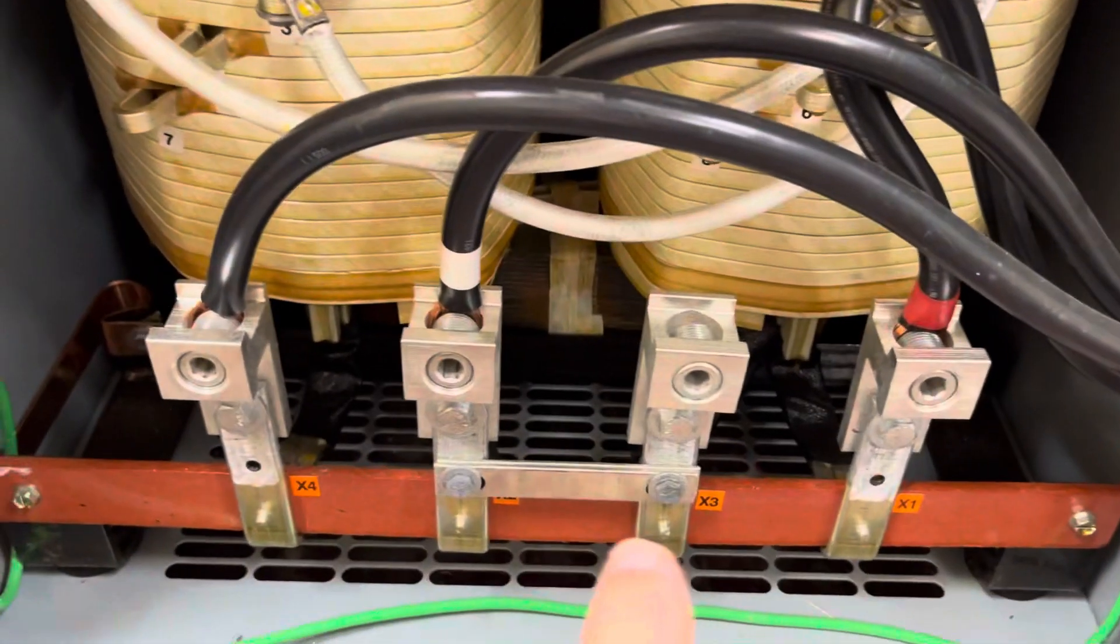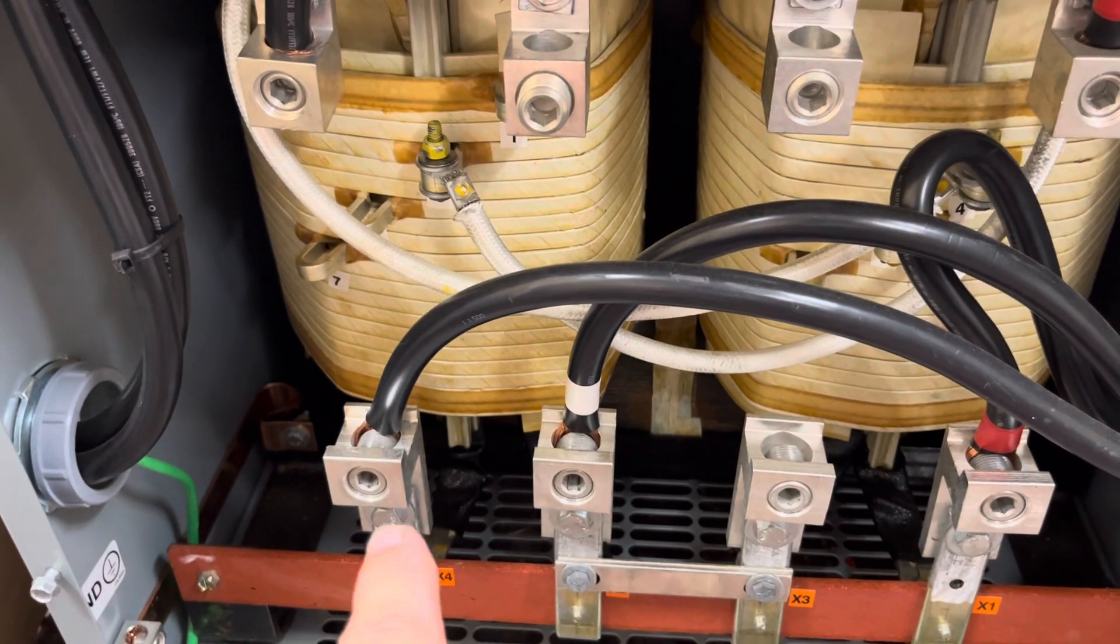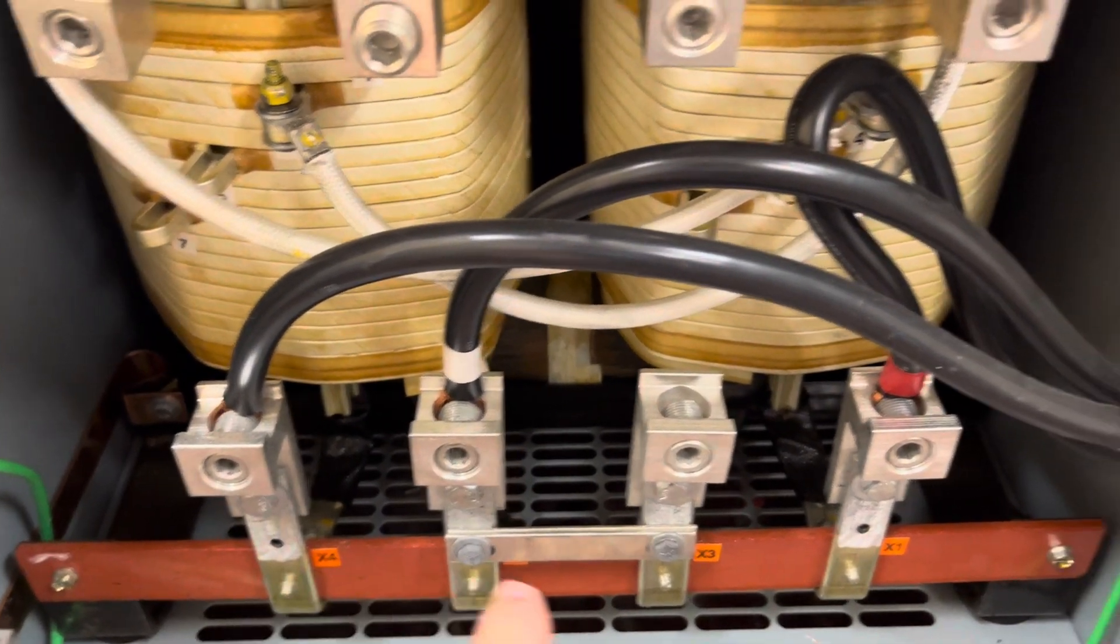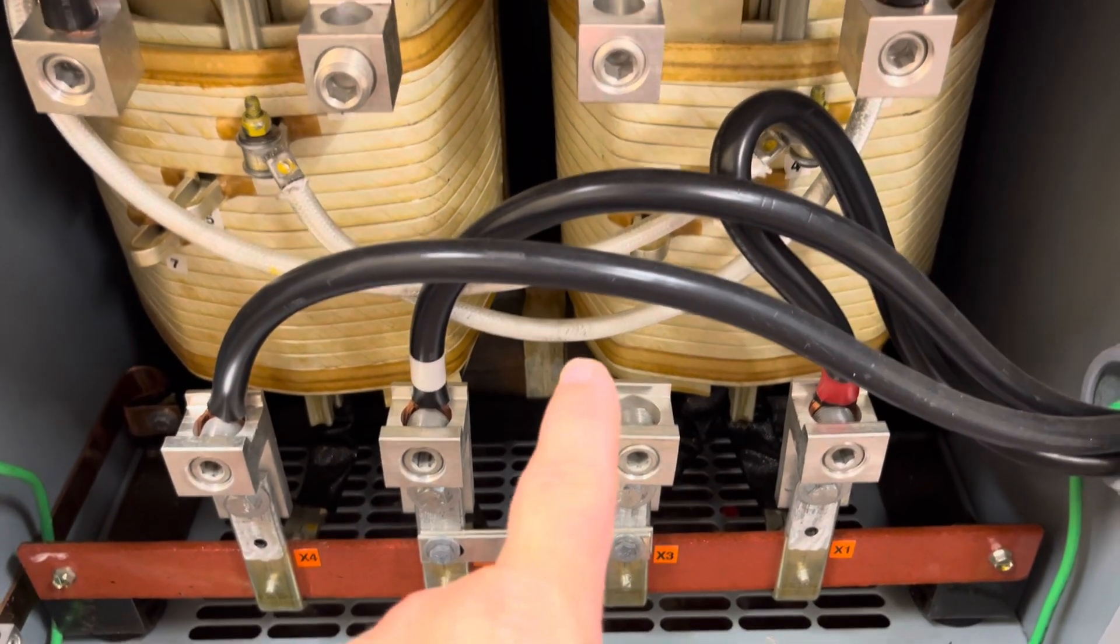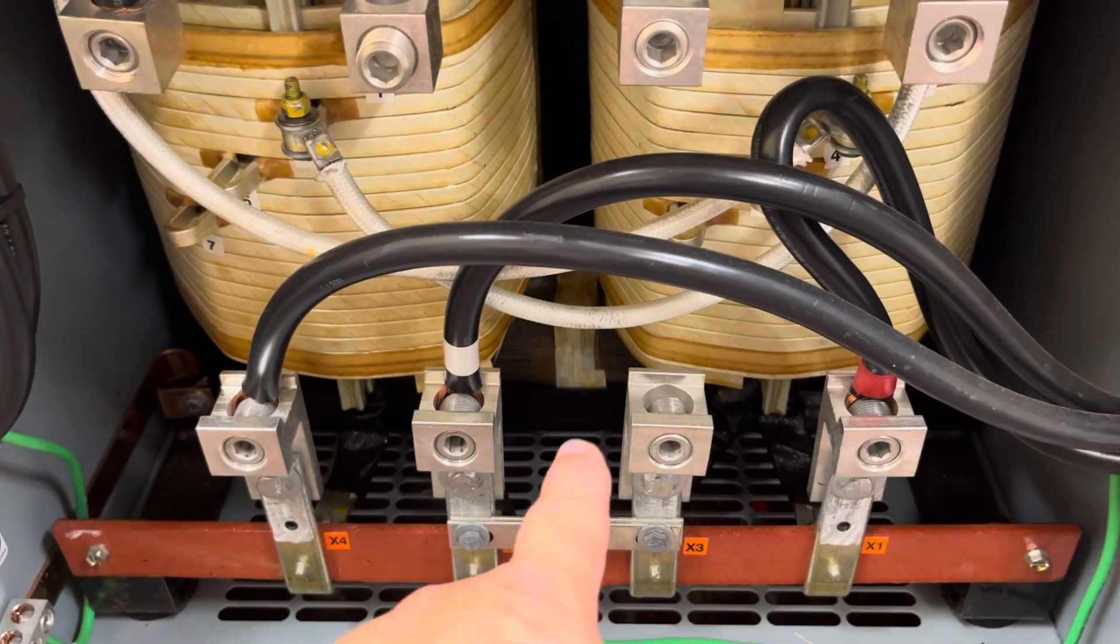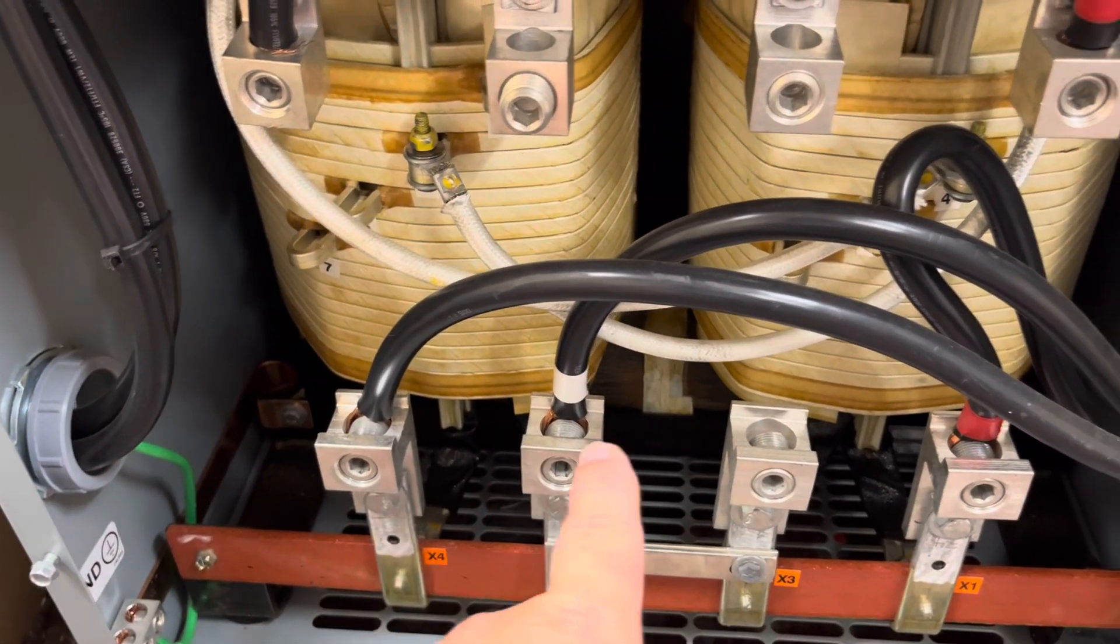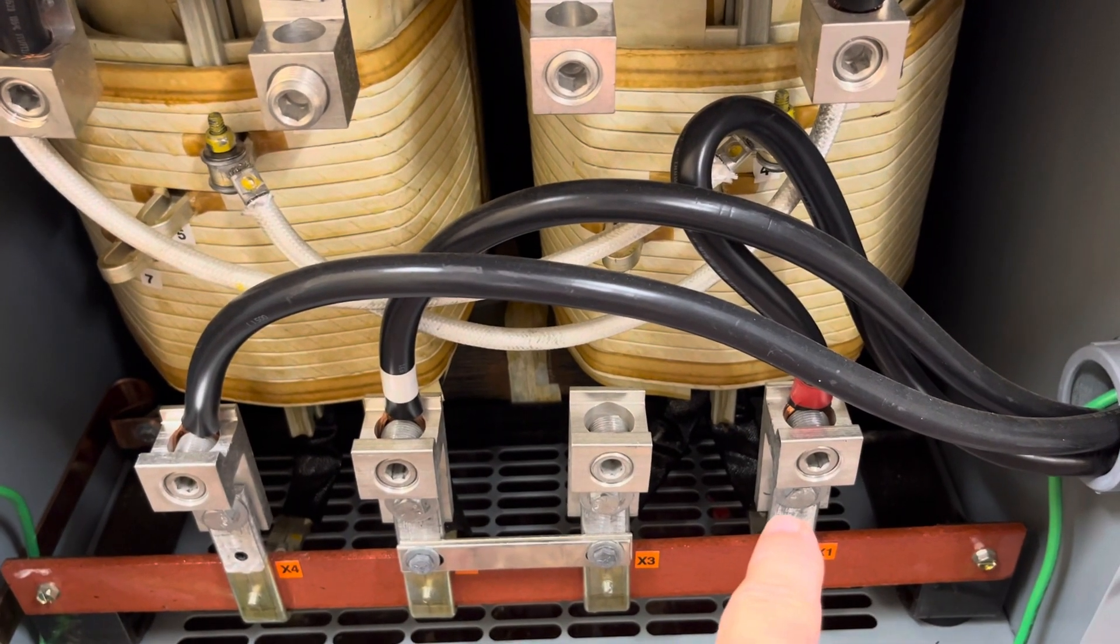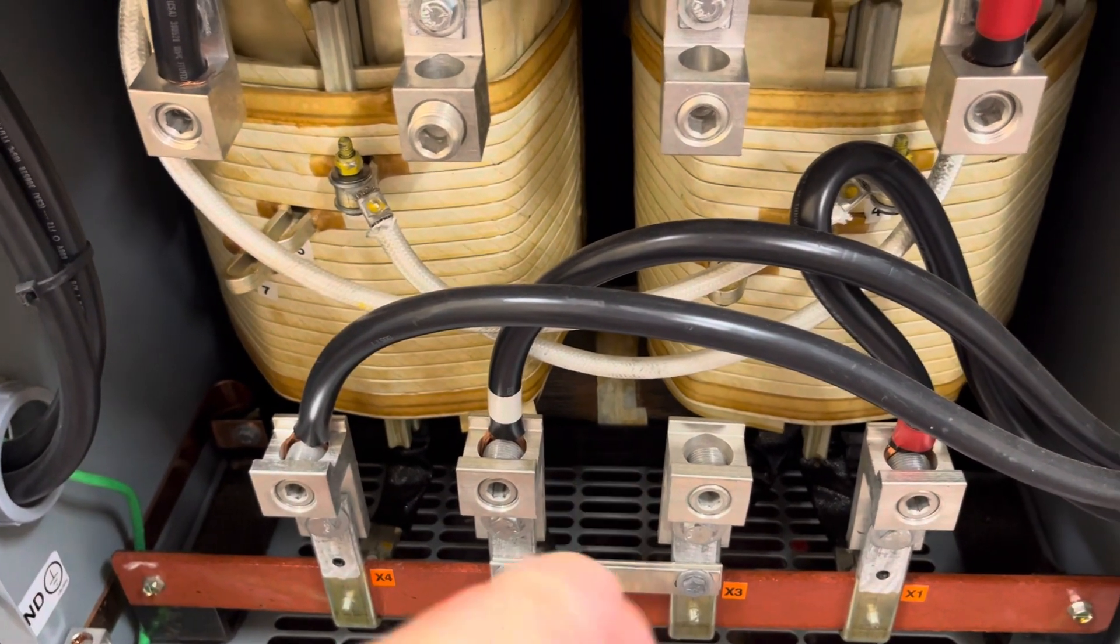Let's just use this down here for example. You would bring in on an auto transformer, you bring in 240 volts from one end of the winding to the other end of the winding. And it has a center tap that you're connecting your neutral to. And since it's in the center, you've got 120 volts referenced from the neutral to L1 and 120 volts from the neutral to L2. That's how the auto transformer is generating the neutral.